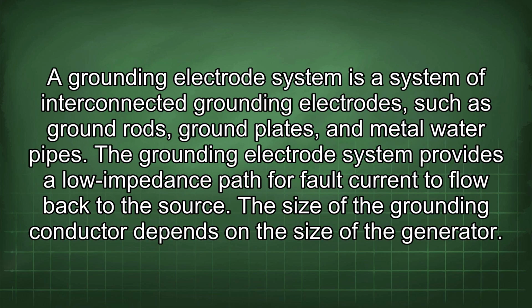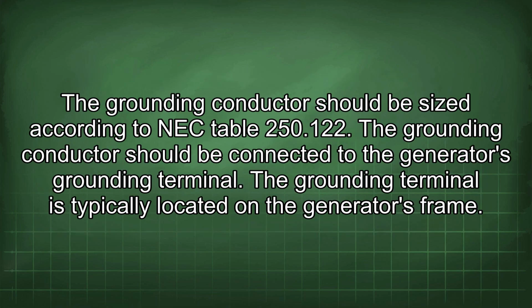A grounding electrode system is a system of interconnected grounding electrodes, such as ground rods, ground plates, and metal water pipes. The grounding electrode system provides a low-impedance path for fault current to flow back to the source. The size of the grounding conductor depends on the size of the generator. The grounding conductor should be sized according to NEC Table 250.122. The grounding conductor should be connected to the generator's grounding terminal.